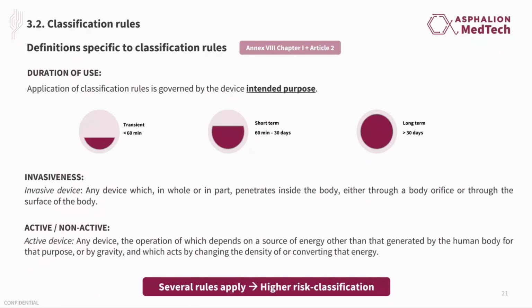So, prior to applying the rules, there are many important definitions specific to classification rules included in Article 2 of MDR and in Chapter 1 of Annex 8. For example, we have duration of use. Classification is influenced by how long a device is intended to be used. Devices are categorized as transient, less than 60 minutes, short term, between 60 minutes and 30 days, and long term, more than 30 days. We also have, for example, invasive devices. An invasive device is any device which penetrates inside the body either through an orifice or the body surface.